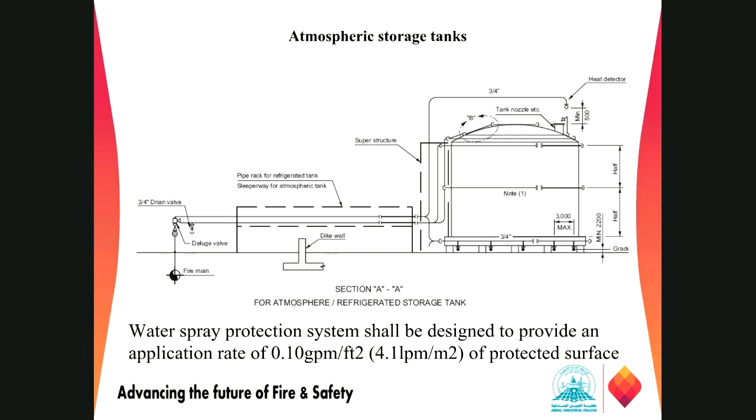And then we have atmospheric storage tanks, right? This storage tank should also be protected by the water spray system, right? We have dike wall areas, and the deluge valve should always be installed outside the dike wall area for fire safety concerns.